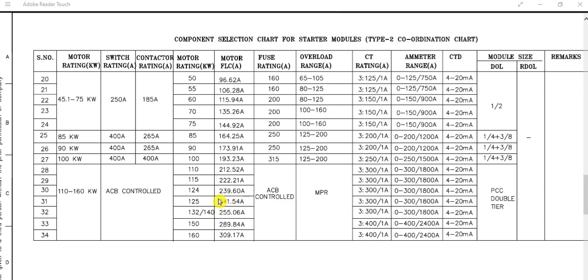So these modules are bigger in size. This is PCC double tier formation. You can see this size is much higher than the contactor operated starter module. So here again this is the component selection chart for the starter module, and this is the type 2 coordination chart provided by one of the vendor panel suppliers.